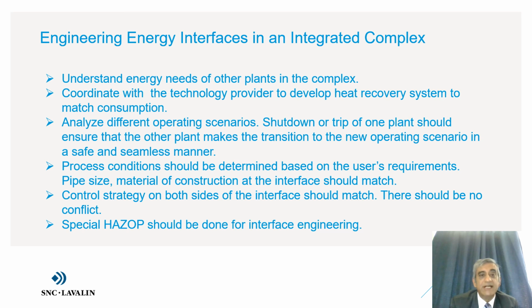It's important to understand the engineering of energy interfaces in an integrated complex like this. Number one, you have to understand the energy needs of other plants within the complex. The engineering company needs to coordinate with the technology provider to develop a heat recovery system to match the consumption. We have to analyze different operating scenarios. Shutdown or trip of one plant should ensure that the other plant makes the transition to the new operating scenario in a safe and seamless manner.